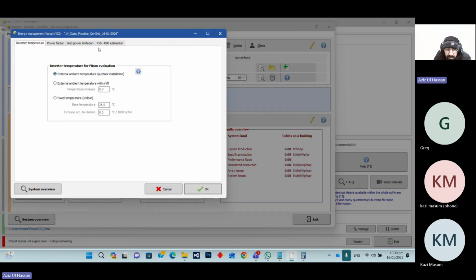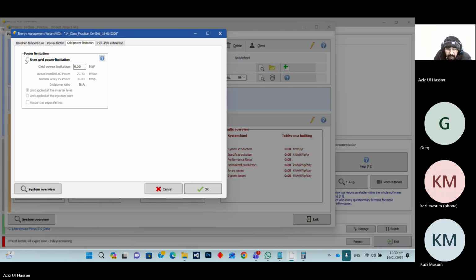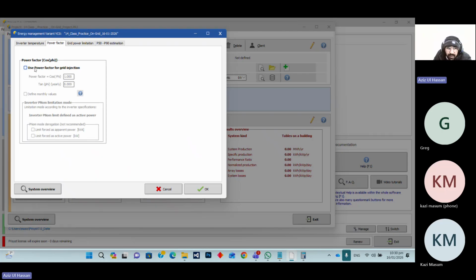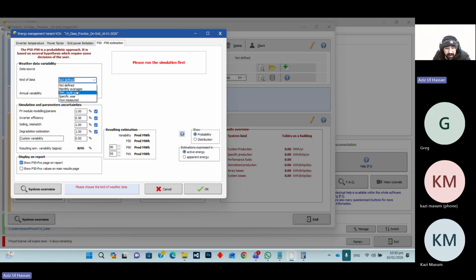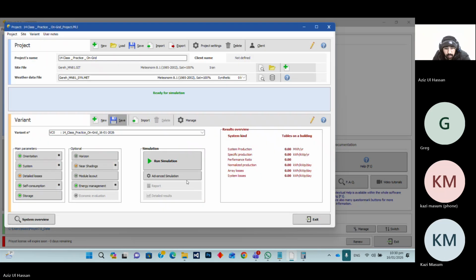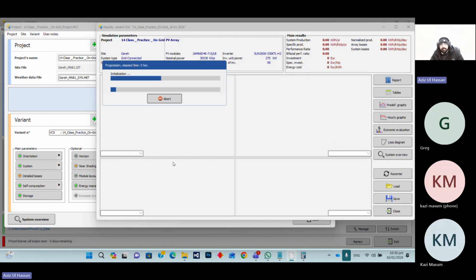Then energy management system. If we have grid limitations, I will apply a grid limitation of 25 megawatt at the inverter level, limit at the injection point. So we are using it as an injection point. Power factor should be 0.95. Most clients will require that it should be 0.95. And then this is the PVsyst method. So I'm just simulating those options.